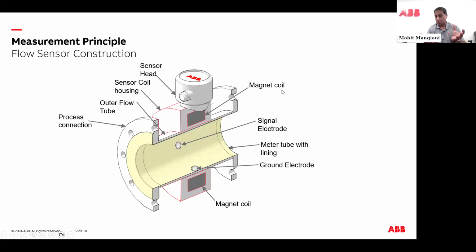You have coils. These are basically coils that generate the magnetic field. You have electrodes. These are metallic items inside of the liner that capture the voltages being read when you run that conductive liquid through the magnetic field. This is your meter tube, like I said, the inside of the piping. And then in some cases, you'll have grounding electrodes, and the magnet coils are typically at 12 and 6 o'clock. So that gives you a feel for how it's made and what goes into the making of a magnetic flow meter. The other consideration is that mag meters are a process device, so they're touching your process, whether it be acid or basic, though obviously it has to be liquid. The only things wetted here are your liner and your electrodes. So anything you put inside your process, you need to make sure those two items that are touching your process are specified correctly for installation considerations.